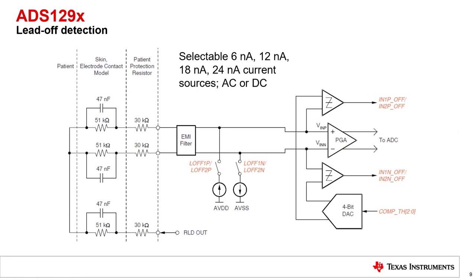The ADS129X also integrates leadoff detection using integrated programmable current sources with very high input impedance. In DC leadoff, current is injected onto the patient and then the voltage is measured by two comparators, one on the high side input and one on the low side. Each comparator reports its output continuously to a status word that is output with each sample.